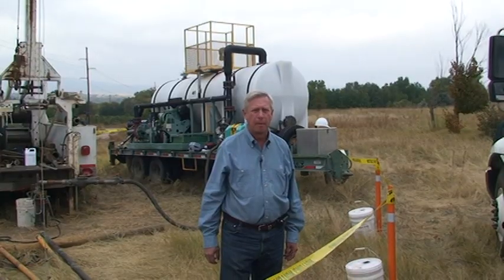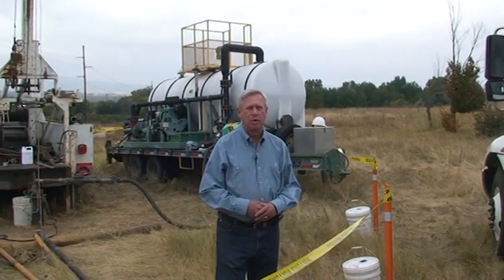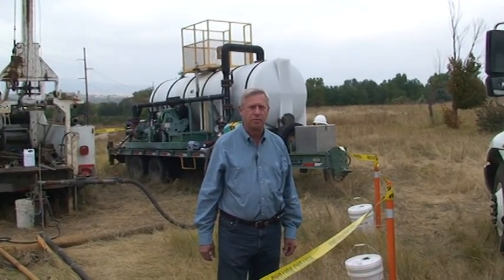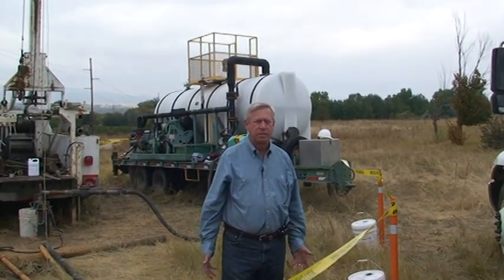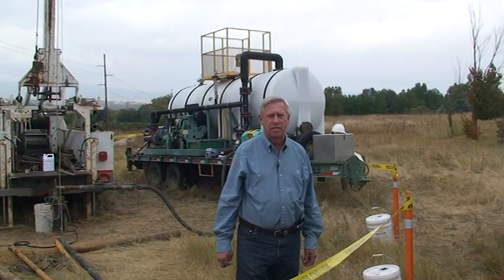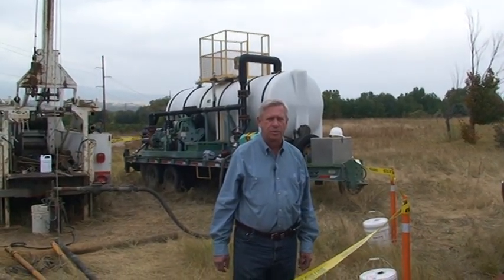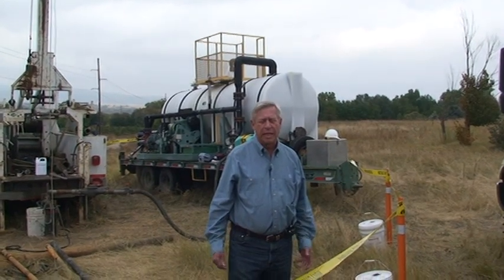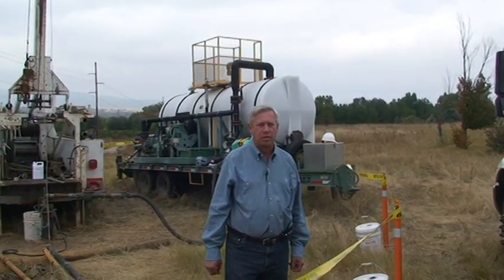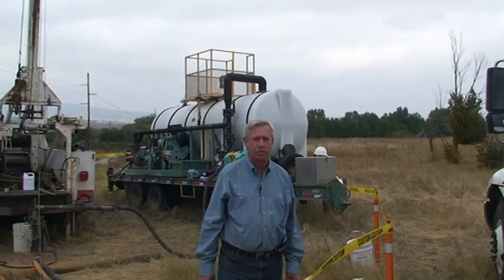Wonderful. Tell me a little bit how Jehn Water Consultants got involved in this whole situation. Well, we're the water consultant for the town of Sedalia, and we do water rights and water supply consulting for the town. We got involved with this particular well because it has been failing over time, losing production, and we were asked to provide some examples and opinions as to what to do with the well. So our opinion was that the well would need to be cleaned up because it is an older structure.